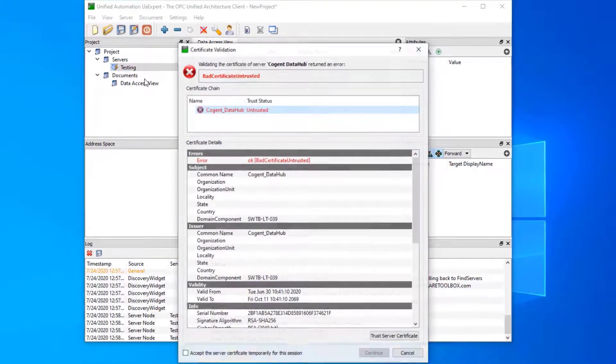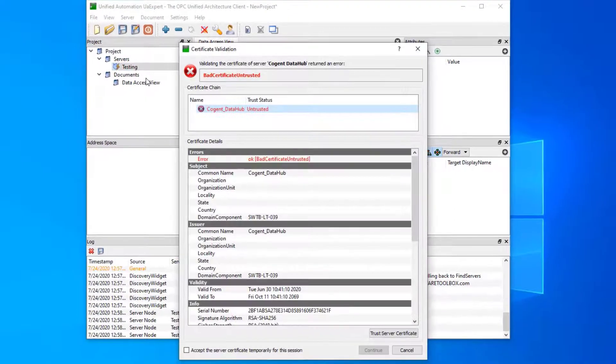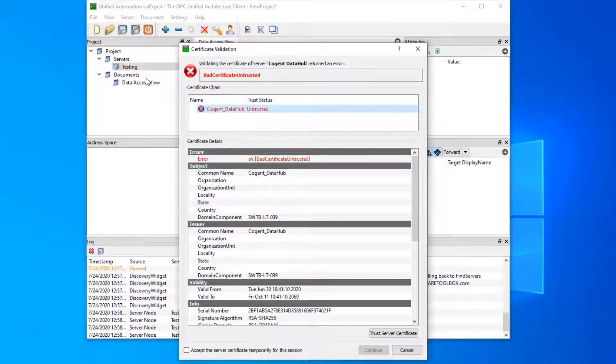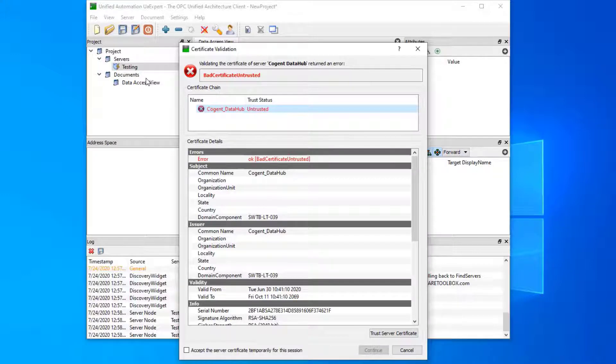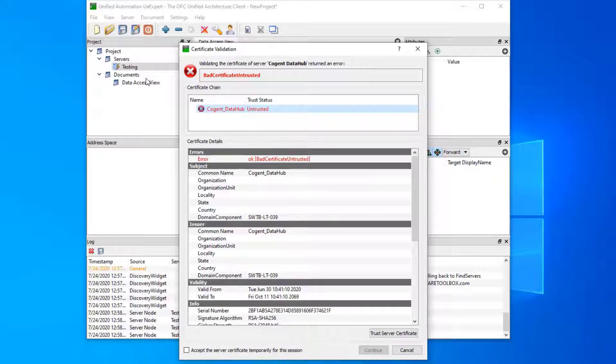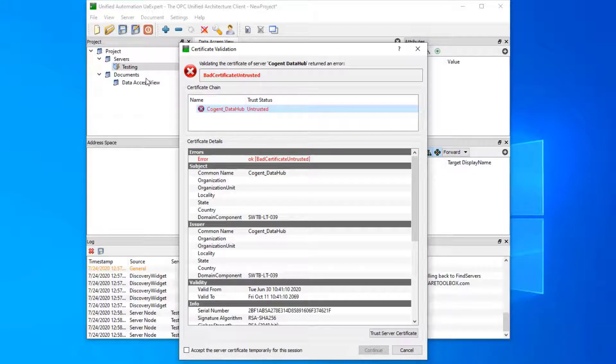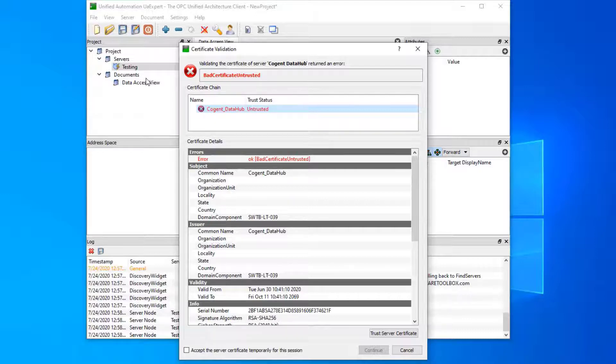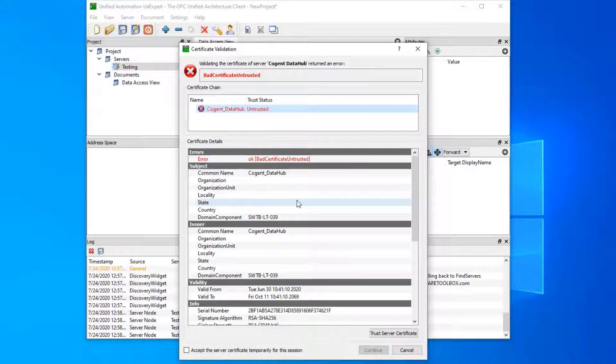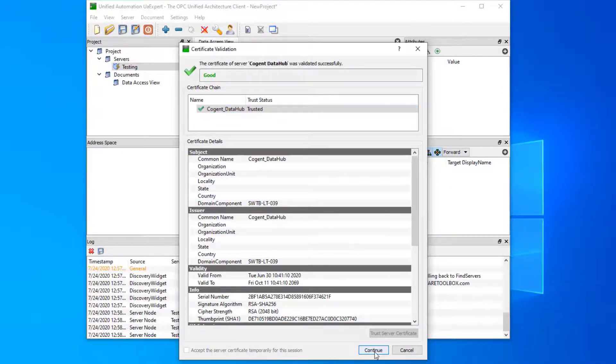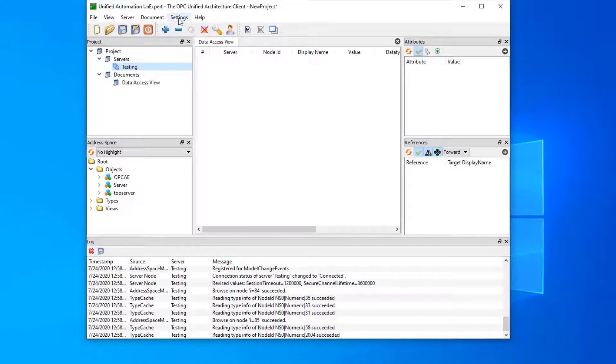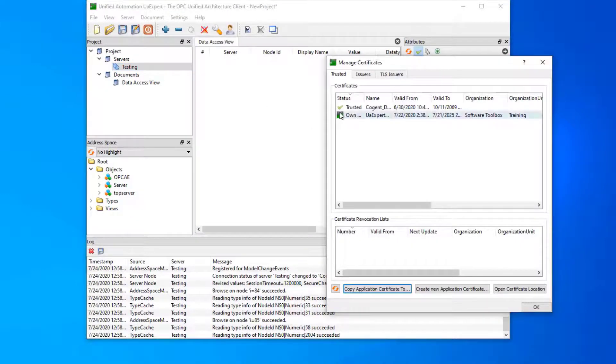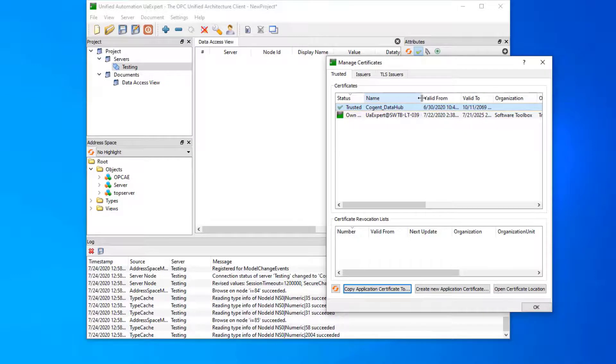When we try to connect to this, this is expected. In this case, the OPC UA expert does not know about the data hub certificate, and what it says here is: do you want to trust this certificate? Currently it's untrusted. If we want to communicate with data hub, we need to trust this on the client side. Now even though we're using no security, this client does require certificates to be trusted in order to gain communication. Some clients do that, some don't. So depending on your client and what security you use, you may need to trust the certificate. So let's trust this one and continue. If we go to our settings and manage certificates, you can now see that our data hub certificate is trusted. That's great.